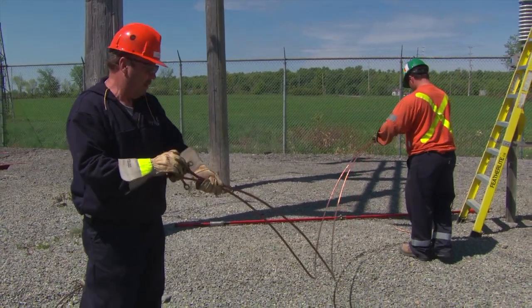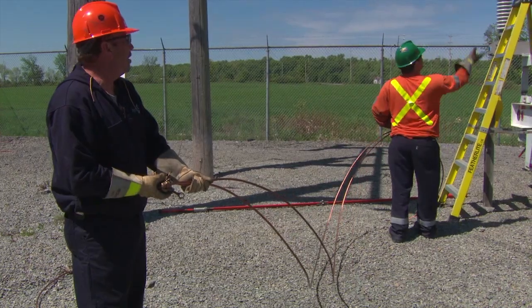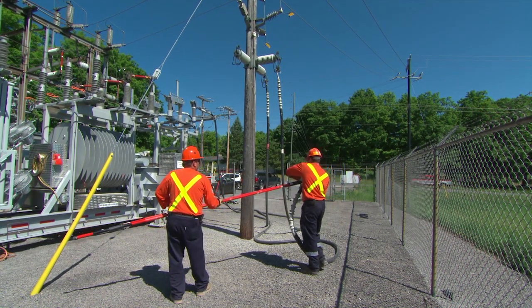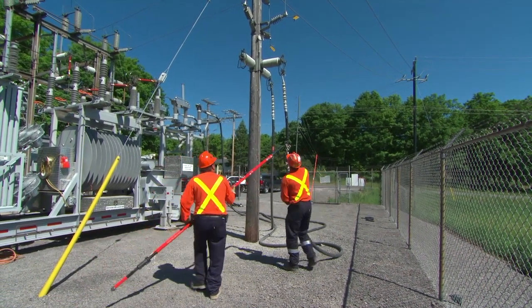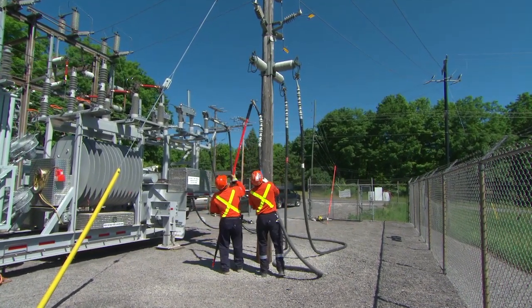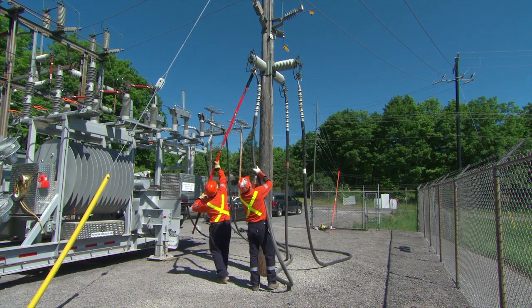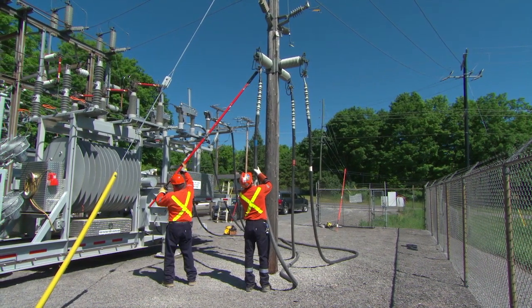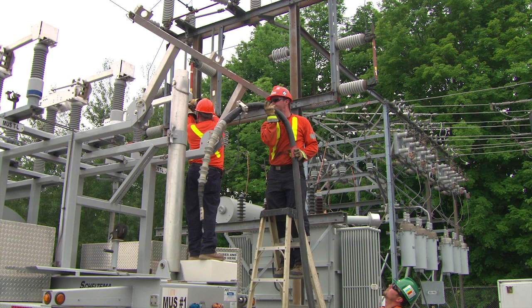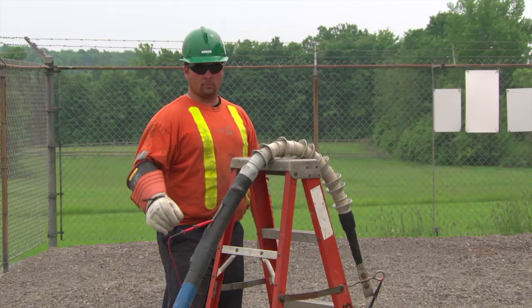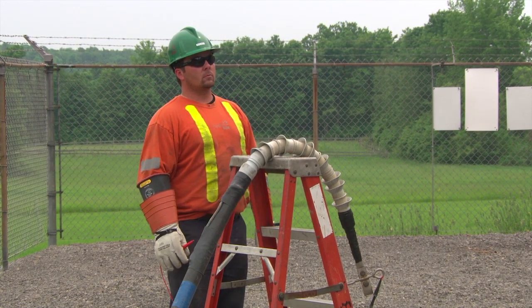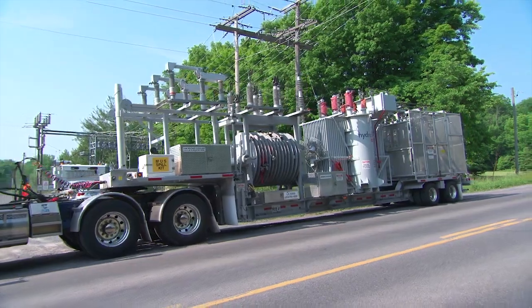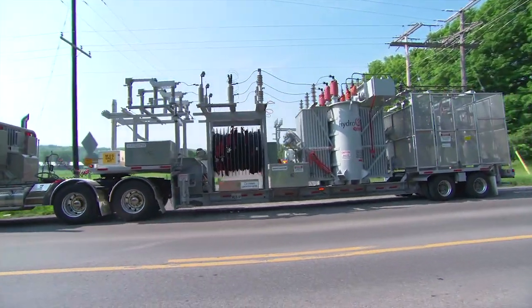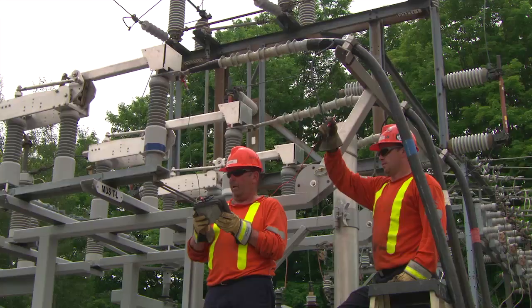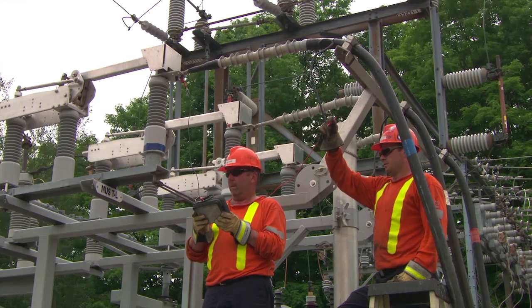High-voltage cables. Typically, the high-voltage supply of the MUS is connected using bare copper conductor. However, some 44 kV mobiles have high-voltage cables that can be used for this purpose. They have the same basic makeup as the low-voltage cables, but they are 250 MCM and rated at 46 kV. The typical length is 50 feet. These cables are wrapped up and brought to site as required. However, some new mobiles are designed with a cable reel that will accommodate them. High-voltage cables can only be used on mobiles that are equipped with a designated support bracket.